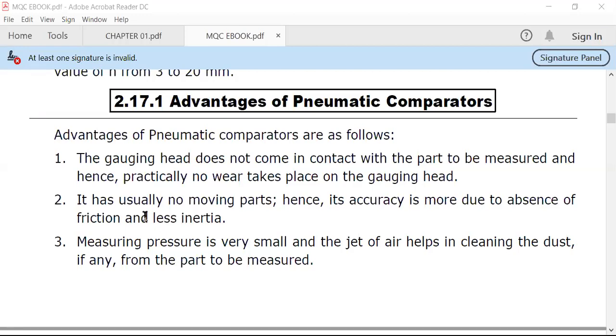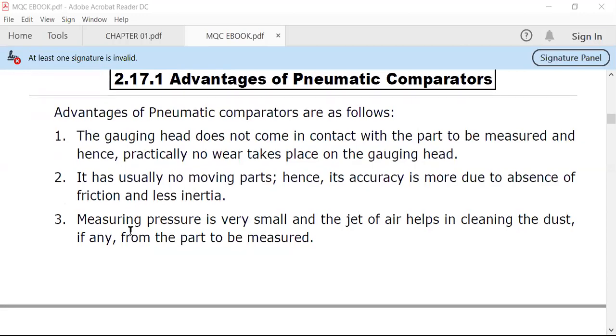Now, the measuring pressure is very small, and the jet of air helps in cleaning the dust, if any, from the part to be measured. This means whatever measuring pressure we apply for the measurement is very small, which also helps clean dust and dirt so you get an exact reading, with no effect of dust and dirt.